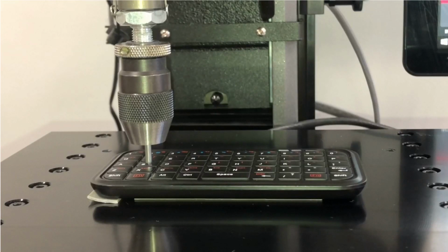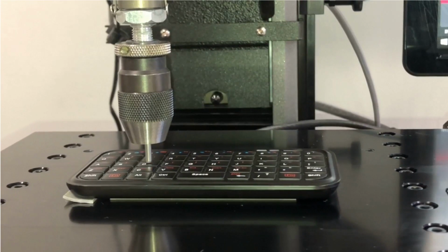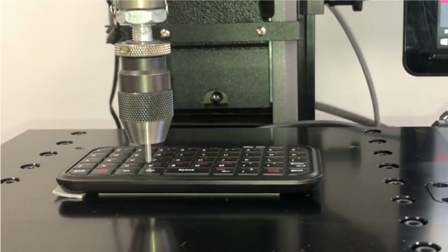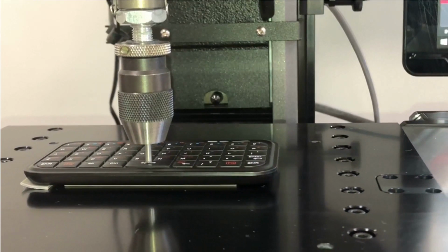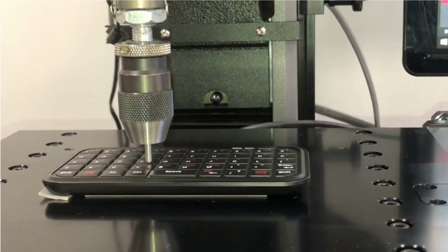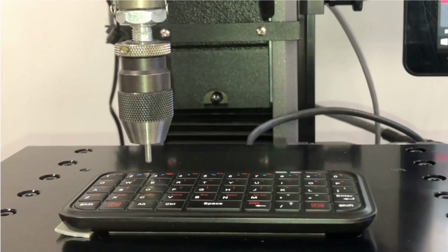In this video, we see a mini USB keyboard under test. A small keyless chuck is used to hold the test probe. The particular keys that are being tested, such as the space key, are set up in the software. After the test is complete, the stage moves into a position to make removal of the tested component and setup of the next easier.